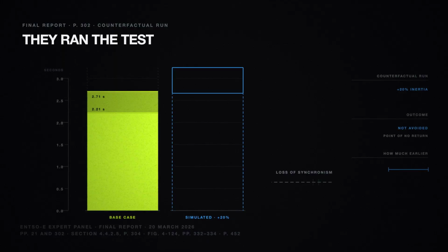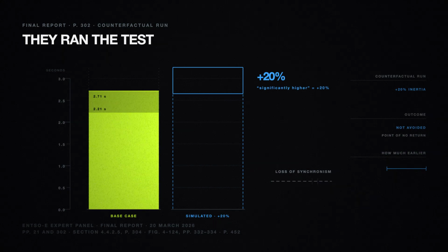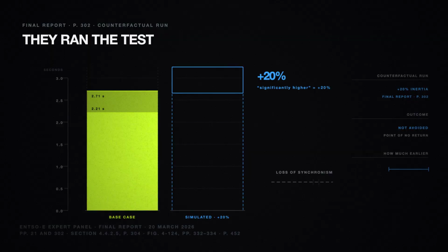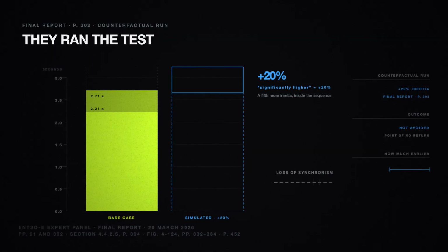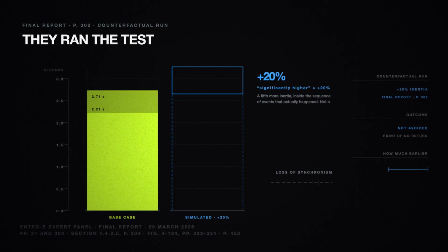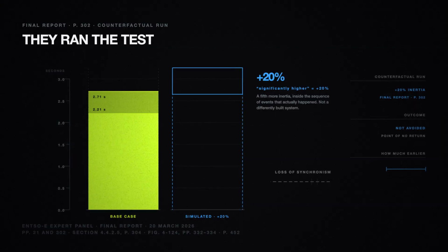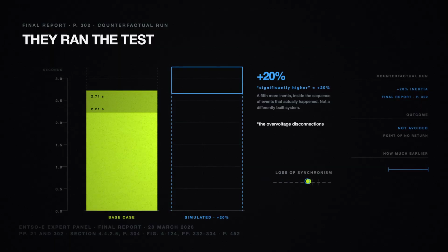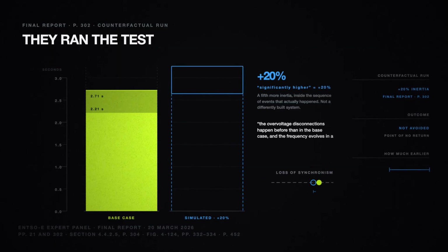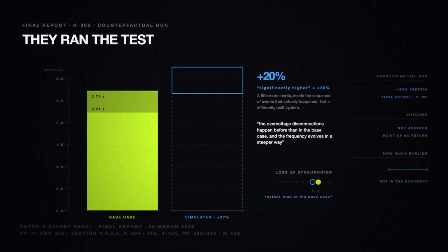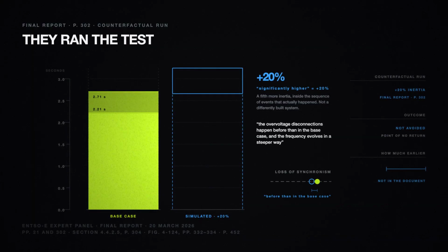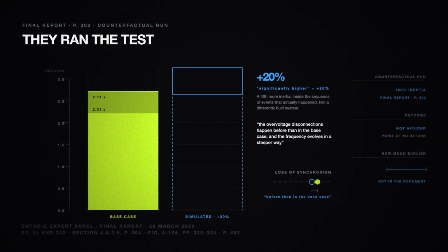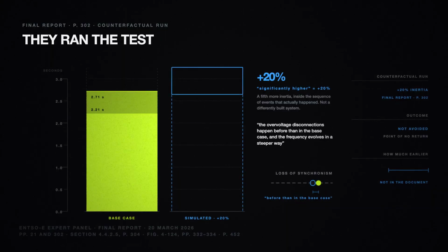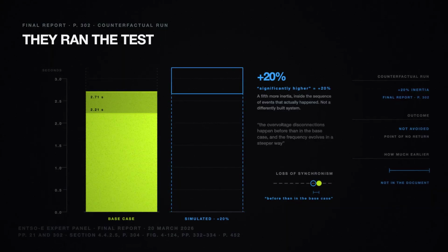Now the caveat, and it belongs here rather than on an end card. Significantly higher means exactly 20%. A fifth more inertia, inside the sequence of events that actually happened. It is not a test of a differently built system. In the simulation, the extra inertia made the outcome very slightly worse. The peninsula injects and absorbs energy with the rest of Europe in a slower and slightly stronger way. The overvoltage disconnections happen earlier than in the base case, and the frequency evolves in a steeper way towards blackout.